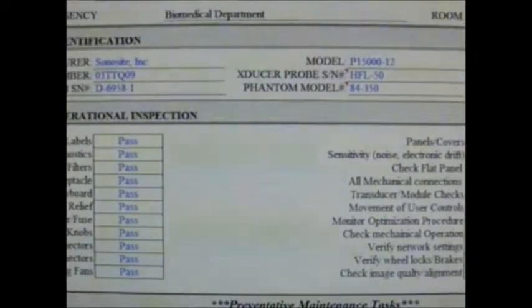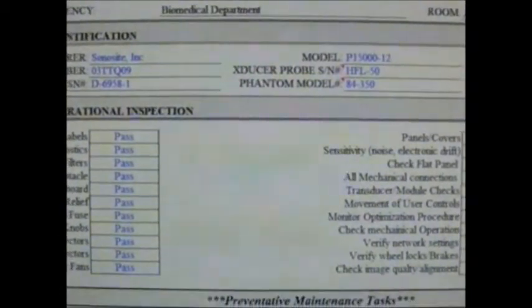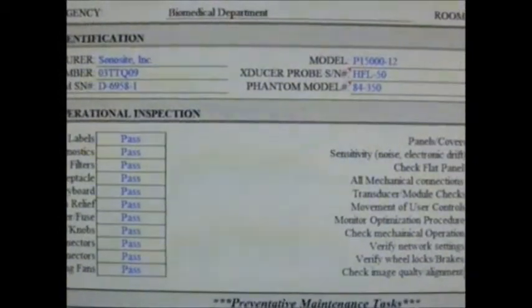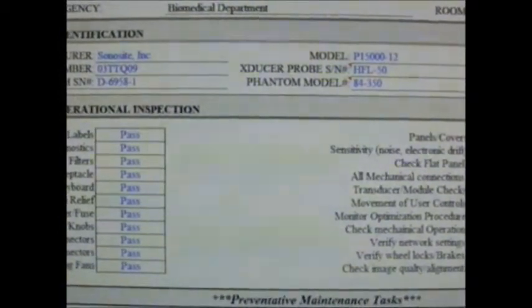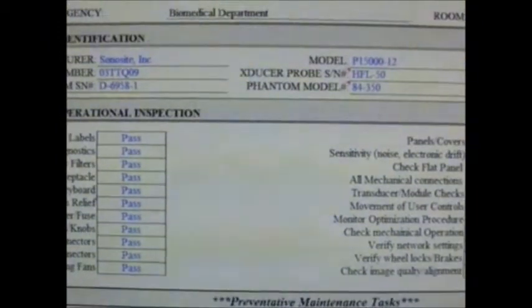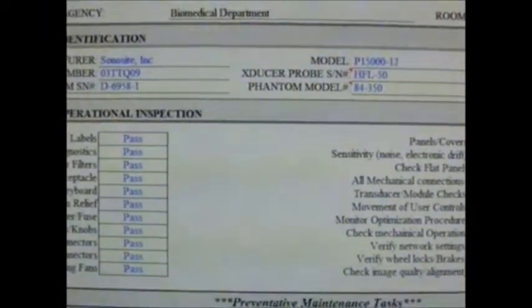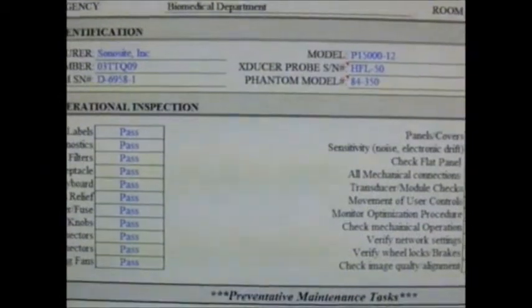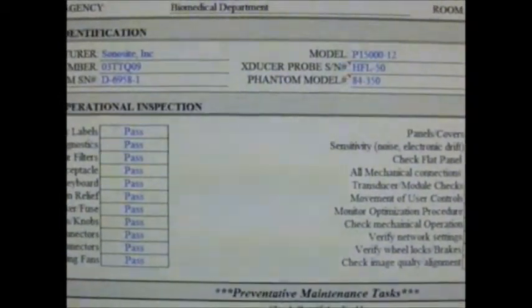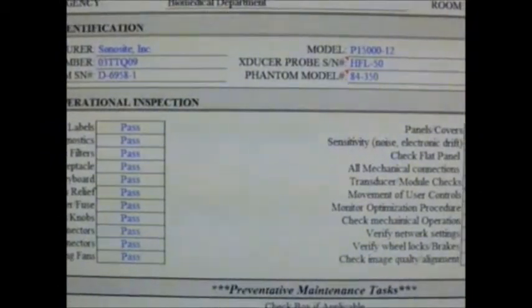This PCI form is going to cover the ultrasound post-calibration inspection or annual quality assurance checks. It's divided into two parts: the top half, which is the equipment identification, and the bottom half, which is the qualitative testing.